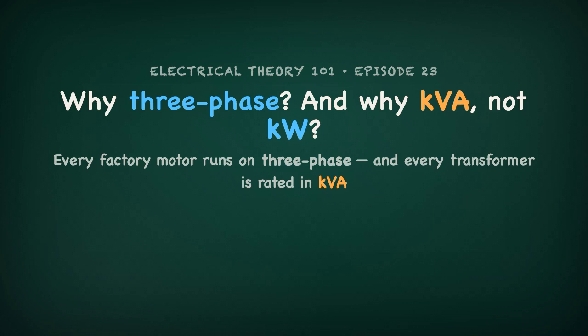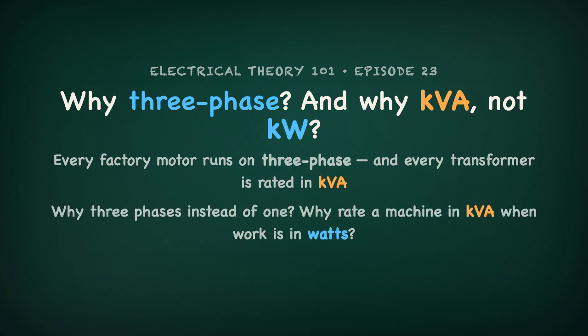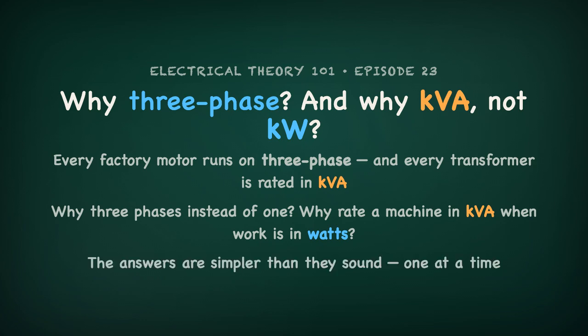Walk into any factory and two things are true. The big motors run on three-phase power, and every transformer is rated in kilovolt amps, not kilowatts. Both of those confuse people. Why three phases instead of one? And why rate a machine in kilovolt amps when the work is measured in watts? The answers are simpler than they sound. Let's take them one at a time.